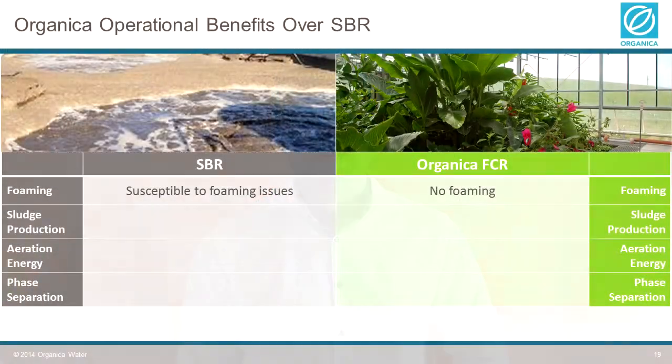Some modified versions of SBRs allow a continuous feed to the basins to offset this issue. However, in these cases, maintaining the sludge blanket during settling and decanting is even more difficult, since the rise in the water level due to continuous filling can easily cause a breakthrough. Therefore, it has to be carried out very carefully.